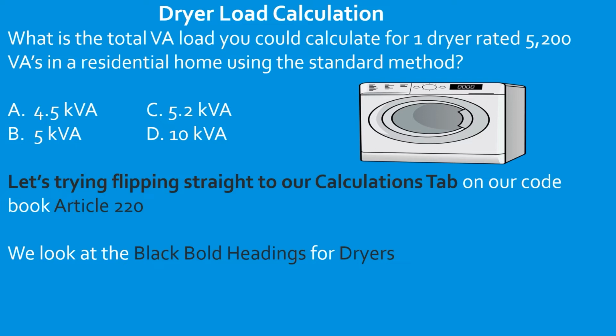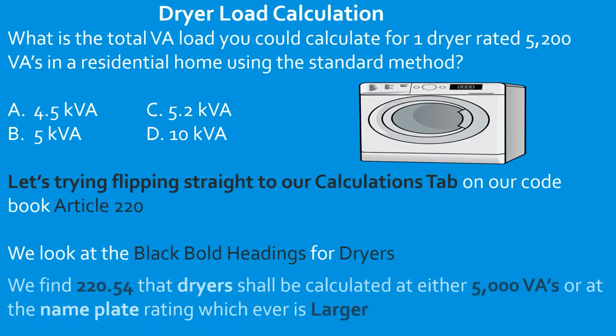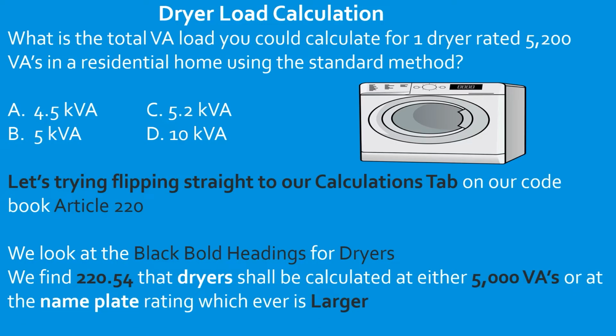Okay, so once we do that, it doesn't take us long to establish where we're at in the code, and we end up right back at 220.54. So that's another way to tackle it, is to use the black bold headings if you feel like you're in the right section. So we end up in 220.54, same rules apply. We have to use 5,000 as a minimum or the nameplate rating. So in this case, we're going to use the larger, and in this case, it's the nameplate rating. So we would actually select C. Great job.